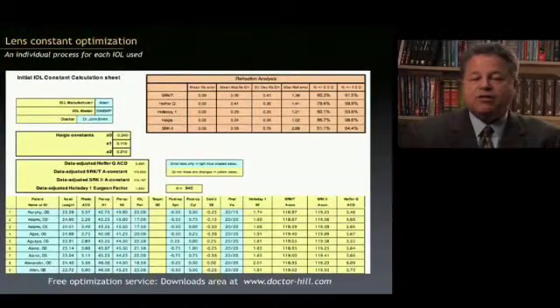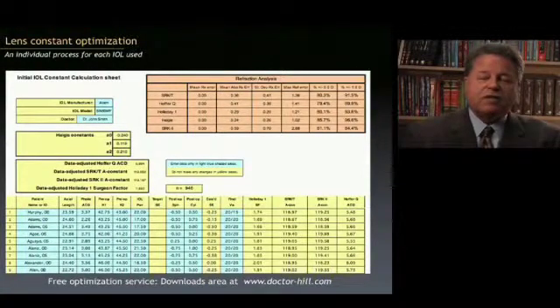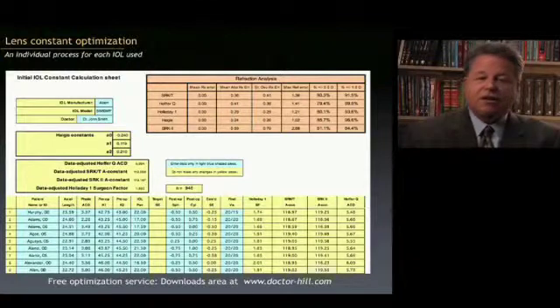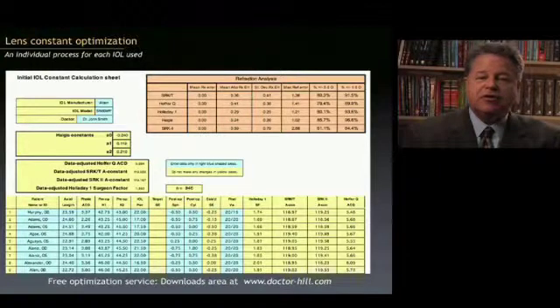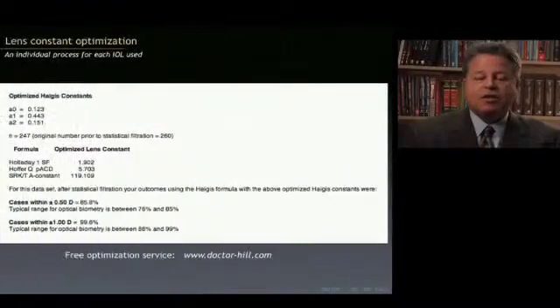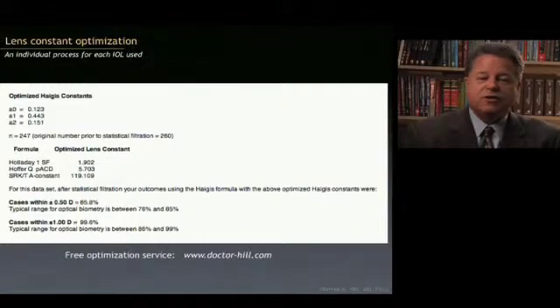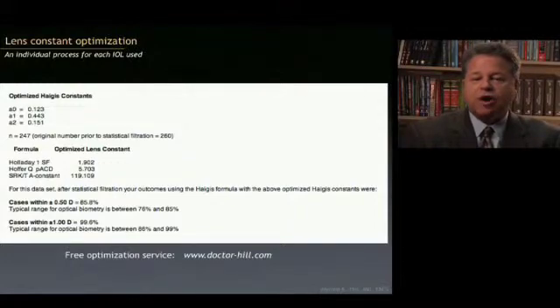Because this instrument is relatively new, most people will need to do some form of lens constant optimization. For the last eight years my office has had a free service where you download a spreadsheet from my website, fill it out with 250 cases, send it as an email attachment, and for free we'll optimize for the basic two-variable third-generation formulas such as Holladay 1, SRKT, and Hoffer Q, and also for the Haigis formula. You'll receive a report showing Haigis constants optimized for your practice, as well as Holladay 1, Hoffer Q, and SRKT, plus a report showing where you stand relative to the rest of the ophthalmic community in terms of accuracy.